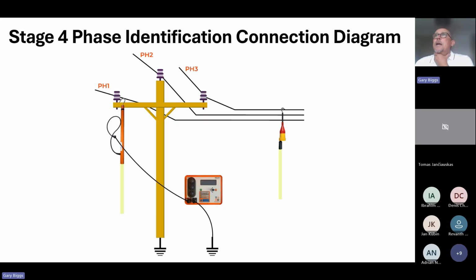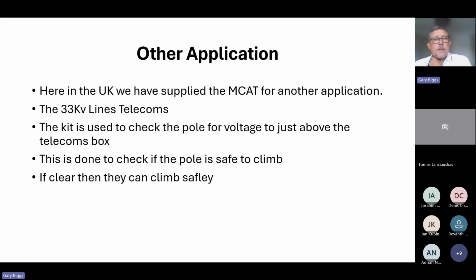But the unit itself, this is a second generation of this unit. We took over HVI in 2020, and at that point, the old version of this had many components that were obsolete, so we were going to discontinue it. We were approached by the Energy Network Association in the UK to bring this unit back from the brink, and when we brought it back, we enhanced it quite considerably. But one of the other applications we have for the unit is on 33 kV systems. Now, this unit is designed for 11 kV systems, and that's where it would be used at this present moment in time. We may look at doing a 33 kV version or other versions according to voltages, but this unit here at the moment is effectively good to 15 kV.